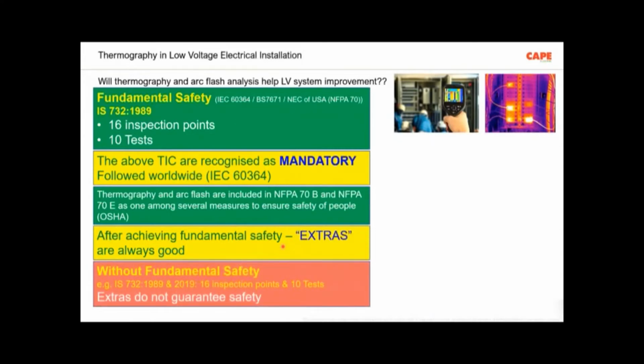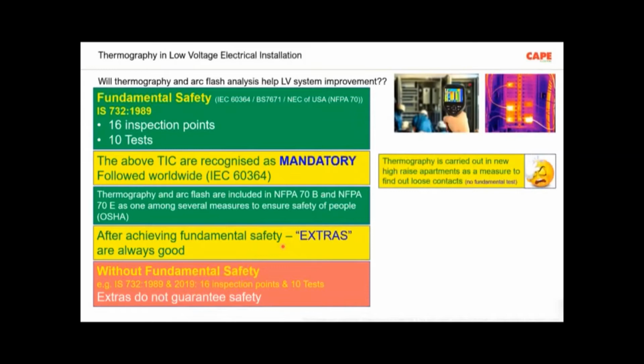But imagine without fundamental safety, if you do only thermography, what kind of guarantee can it give? It cannot give any guarantee. Extras will not guarantee safety. First, you make your fundamental safety proper. Then you do whatever extra things you can, and as a result you enhance the safety. But if you take pictures with a thermal camera and believe that every place is cool and therefore we are not in trouble, that is not the correct way to expect safety. And recently, I even saw a new high-rise apartment building in Bombay where they are doing thermography to find loose contacts in the wiring.